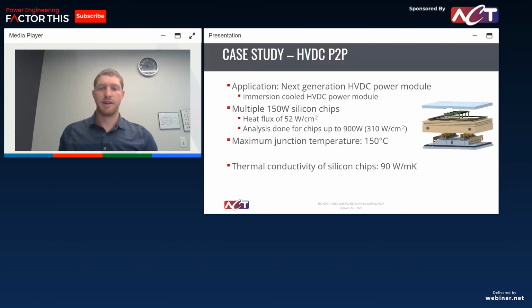So great effectiveness on that one. And now just a quick example for a small HVDC application we use pumped two-phase on. This was a small next generation HVDC power module. It had two 150 watt silicon chips. The heat flux of those chips was only 52 watts per centimeter squared, but they were looking at implementing some chips that had 900 watts, so same footprint, so that would be 310 watts per centimeter squared, and they had to keep that maximum junction temperature down at 150 C.